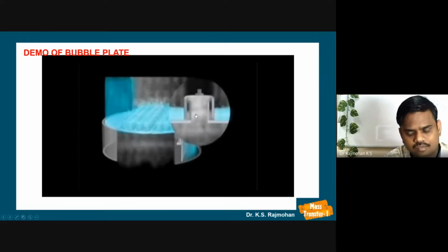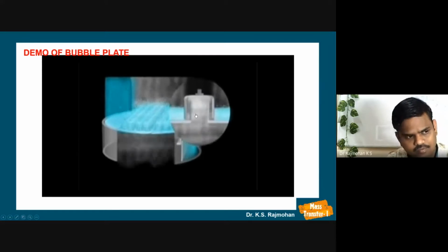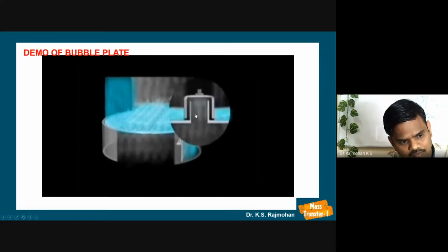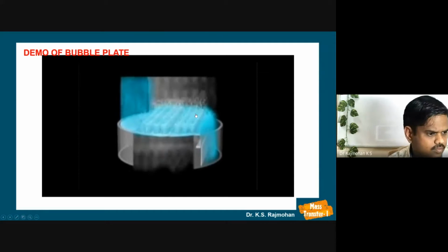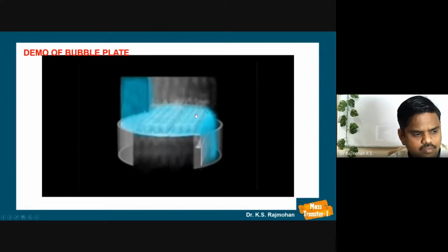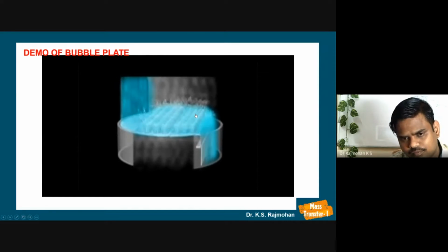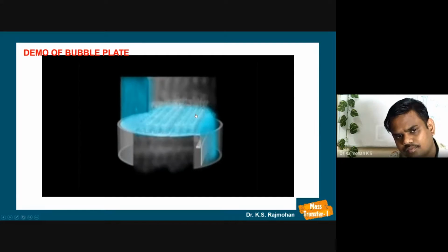And the cap does not enhance the mass transfer. The labor cost of assembling the riser cap units makes these trays more expensive. The weight of these units also leads to support problems on large towers. Consequently, most new applications today are in services where a large amount of vapor must contact a relatively small amount of liquid.